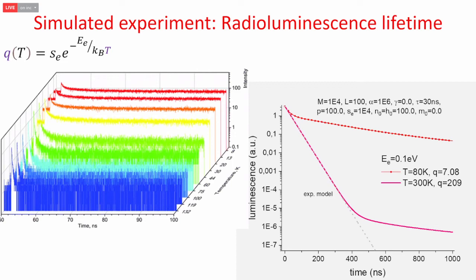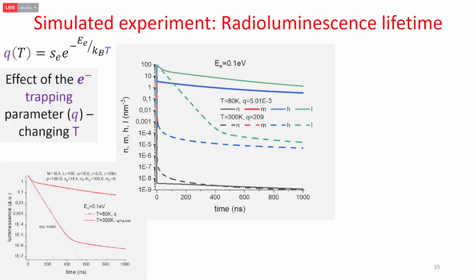It is better to measure, but actually what we can do is that we can ruin the system, because at low temperature, at room temperature, the detector is fast because the trapping is not playing too much importance. But when I freeze or decrease the temperature to like 80 Kelvin, then I start stabilizing some traps that slow down the whole process and ruins the time characteristic of the detector. So this is just a few things that we did.